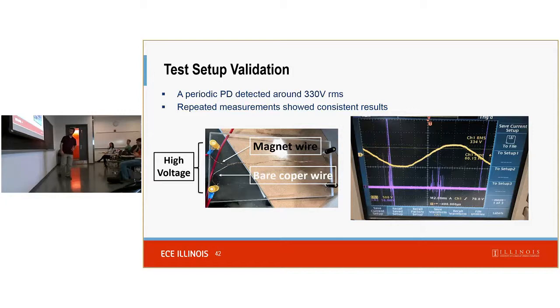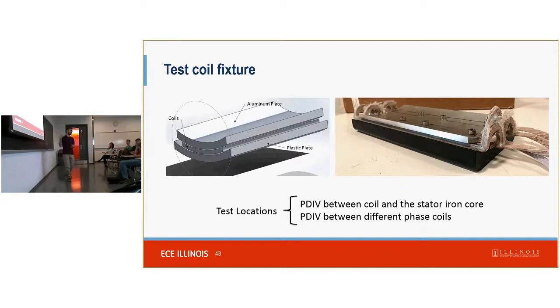And we can see here the test setup validation. By using just wire rather than our coils, we can choose to have wire that we know is really well insulated or poorly insulated and have control there to validate that the setup gives good results. And in this oscilloscope plot, you can see these high spikes. Those are indicating where partial discharge occurs. And there'll be another plot later on where we can see a couple different ones comparing partial discharge and showing a region with and without partial discharge.